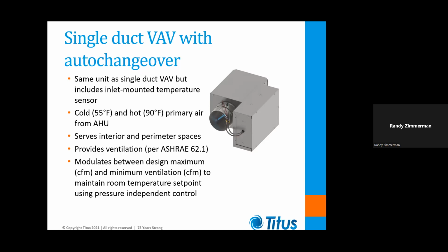So that's auto changeover. Now, with digital controls, we don't necessarily have to have that inlet mounted sensor. The air handler could shoot out a signal, like a global command out to all the boxes telling them whether they're in heating, ventilation, or cooling mode. But of course, in these smaller buildings and smaller systems, that digital control system is rarely going to be set up to do anything like that. So we're back to having an inlet mounted sensor on each box to tell that box's controller what the supply air temperature actually is.